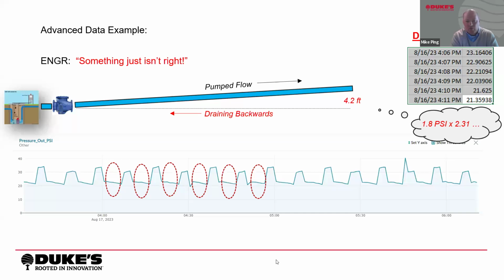There's this 2.31 multiplier, and it's like this thing is losing 4 feet of static head every cycle that the pumps are off. What's that mean? That means that the pump flow should be going through the check valve from the station over on the left and being pumped to the right, and this thing is draining backwards.